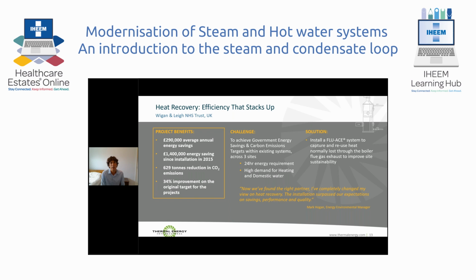The overall savings were around £290,000 per year, and since they were installed in 2015, we've saved over 1.4 million in natural gas for the hospital. This was a 34% improvement on the original projected savings for this project. The customer's been very happy with this site, and we were able to manage the installation to minimise the impact on the critical care units where we were operating, making sure there was sufficient redundancy throughout the work to maintain the operations of the hospital.